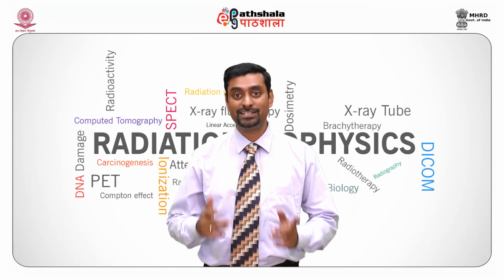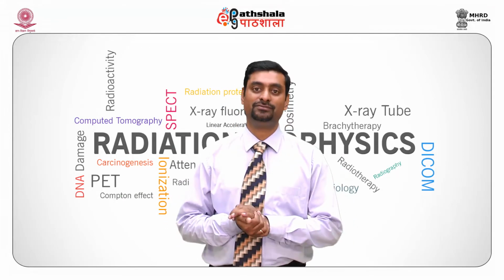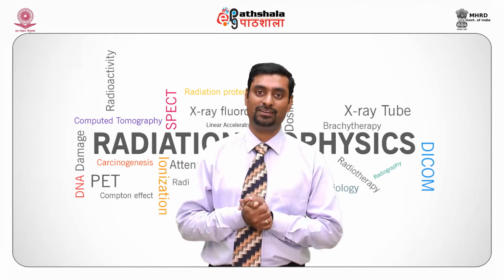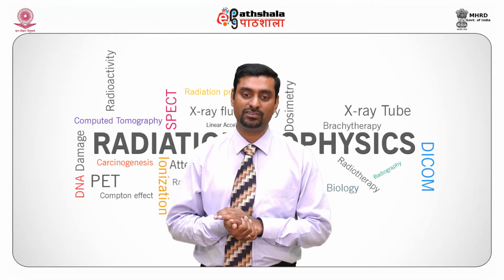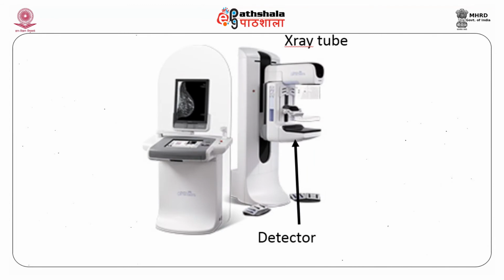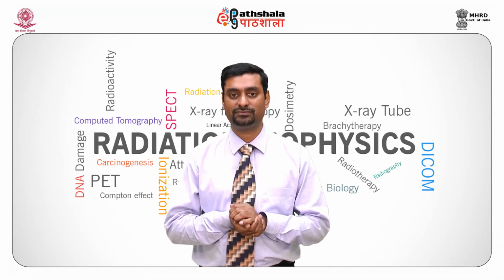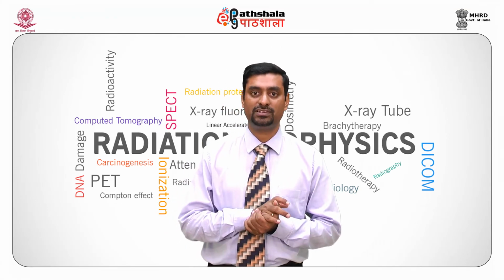onto a monitor. Next, we move on to a direct flat panel technology which does not have a scintillator material in it. Let's see what is there in this technology. The general principle of direct flat panel technology: X-ray photons. As usual, there's an X-ray machine. Instead of amorphous silicon, we have amorphous selenium here. The amorphous selenium is a photoconductor material which directly converts X-rays into electrical signal, followed by a thin film transistor, which is a readout array that acts as a switch, similar to what we saw in the amorphous silicon technology.